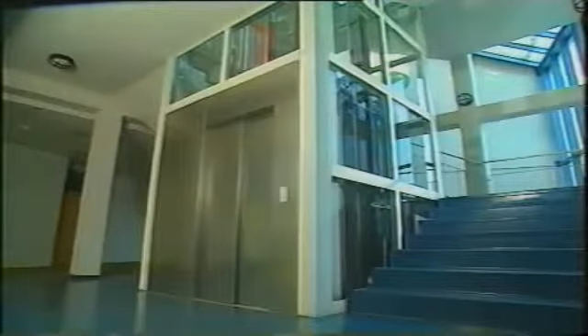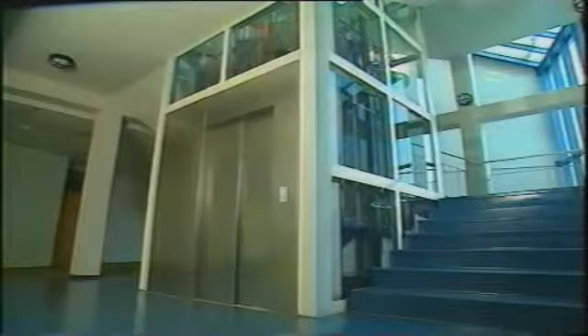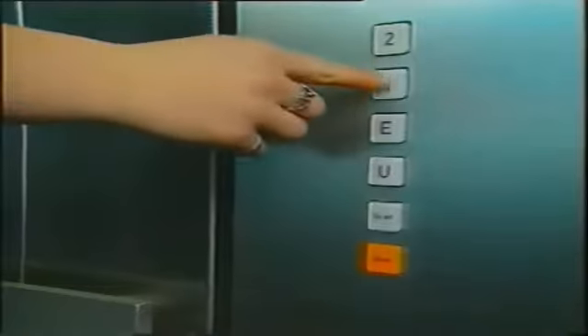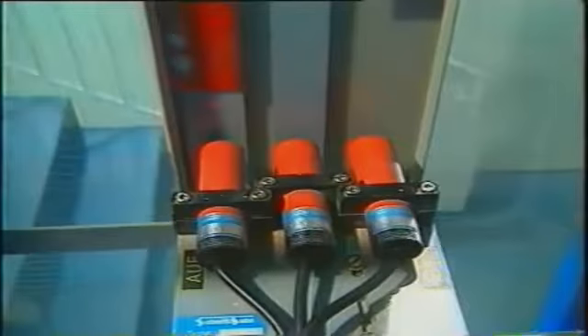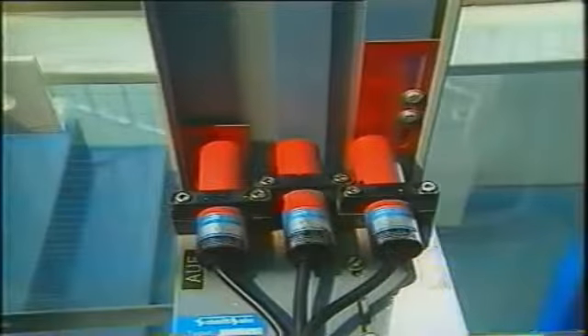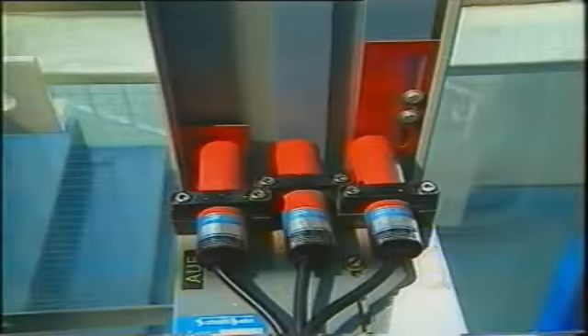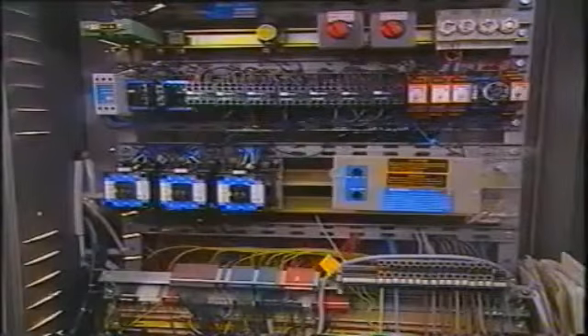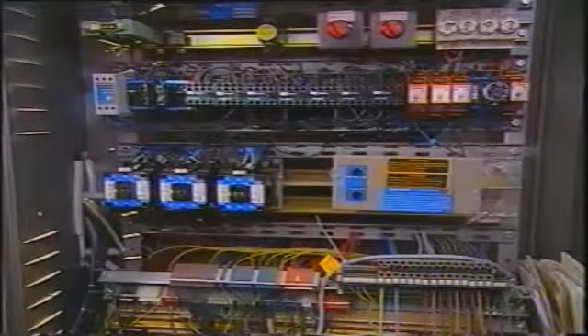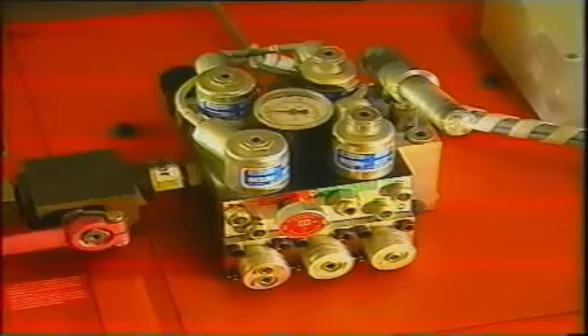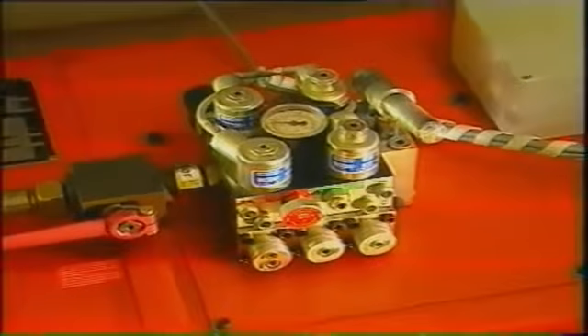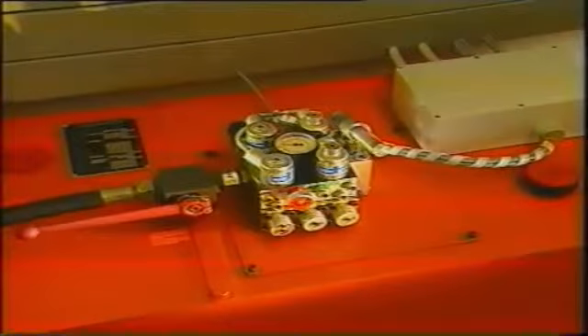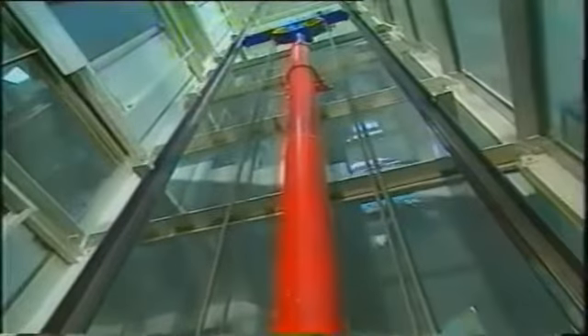Also in the elevator, these two areas are clearly differentiated. The controls in the elevator and on the door and the sensors in the shaft, which report the position of the elevator, together with the controller, form the electrical control part. The solenoid valve is the interface to the power part, consisting of the power pack, the valve in its function as a final control element, and the hydraulic cylinder.